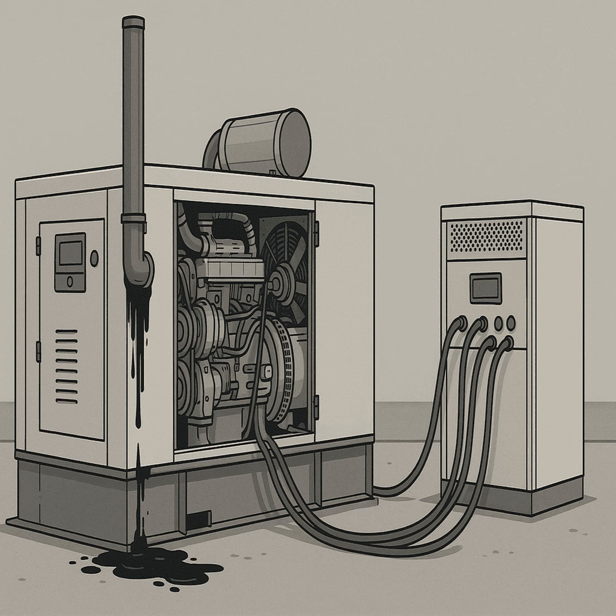Precisely. When a diesel engine runs at less than, say, 30% of its rated capacity for long stretches, and some experts say even anything below 60% can be risky over time, it just can't maintain the optimal operating temperatures. And without that heat, the fuel doesn't burn completely. A significant amount just passes right through the combustion chamber and into the exhaust system as unburned fuel vapor or droplets. That's your wet part.